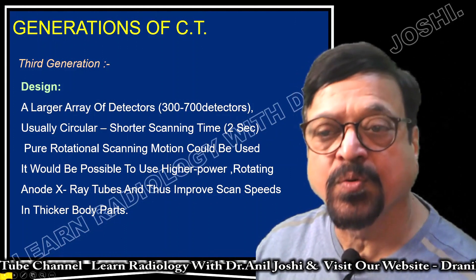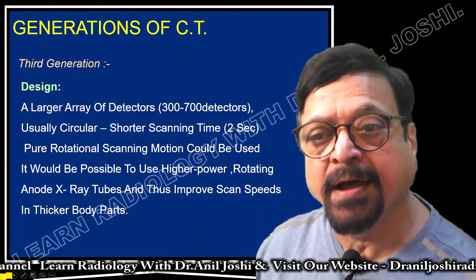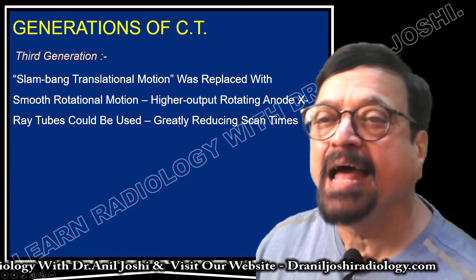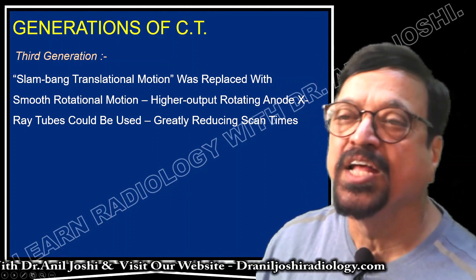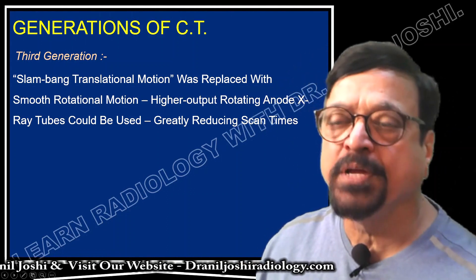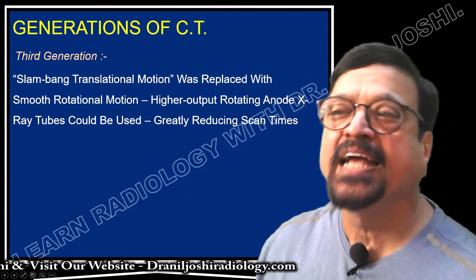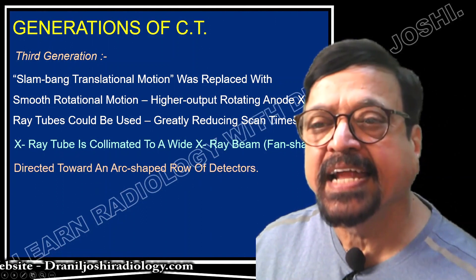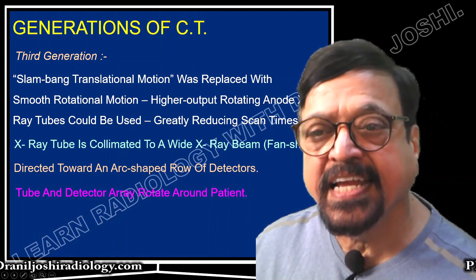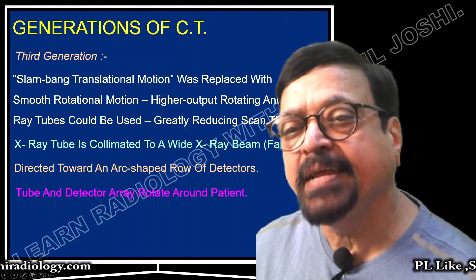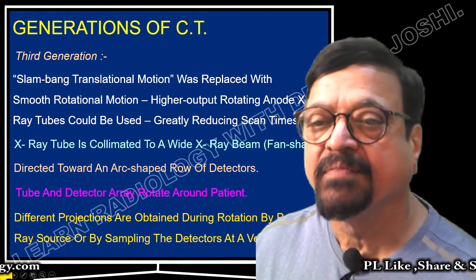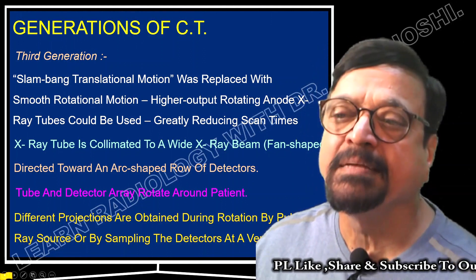What was achieved with the third generation? We could scan a single breath-hold thick body part like chest, abdomen, etc. The back-and-forth translation motion was replaced with smooth rotational motion. Higher output rotating anode X-ray tubes could be used, greatly reducing scanning time. The X-ray tube is collimated to a wider fan-shaped beam directed towards an arc-shaped row of detectors, providing better image quality. Different projections are obtained during rotation by sampling the detector at a very high rate.